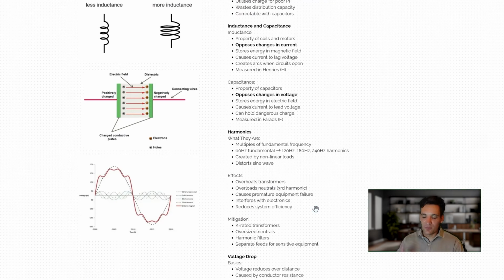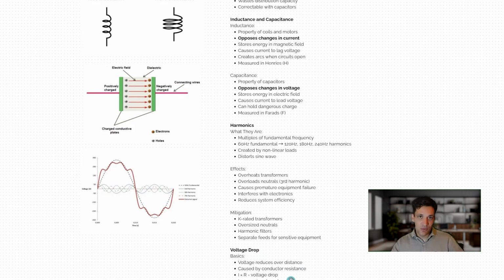And the final concept of power quality issues is voltage drop, which I've already spoken about a little bit when I was talking about why we chose to adopt an AC system versus a DC system. Voltage drop is where you have some resistance in the conductor or the transmission media, and you have a current flowing through it. So if you start with 240 volts, you have current flowing through it, and then you have a resistance in the line. At the actual source where you're going to consume it, or the load, I should say, you might have 230 volts or 220 volts, depending on the losses in the line. The way we mitigate this is that larger cable sizes have less resistance, so you have lower voltage drop.